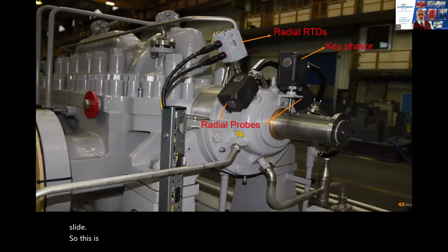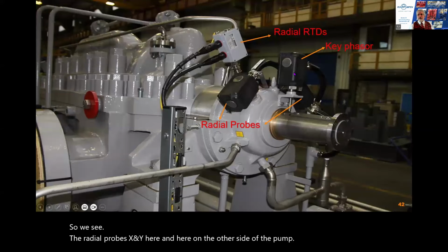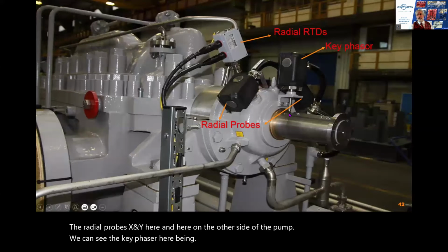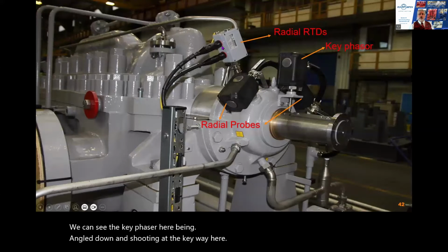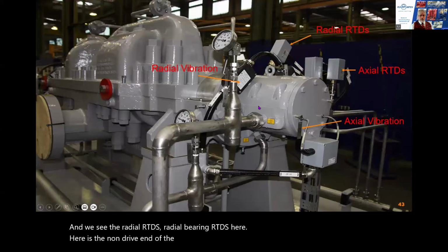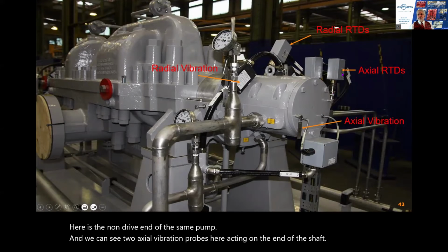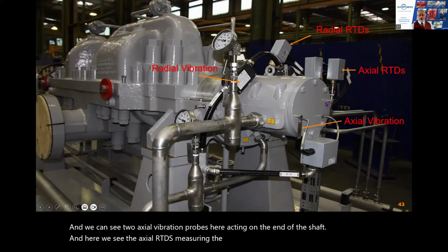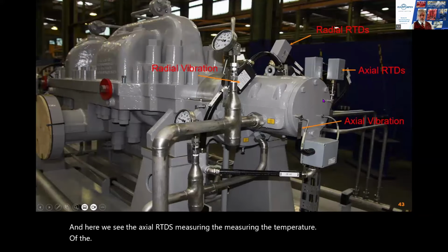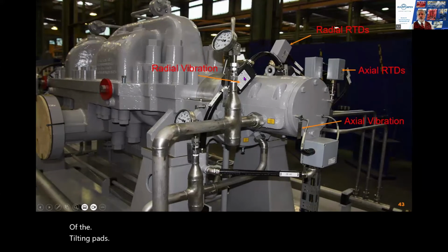So this is another example of a pump with sleeve and tilting pad type bearings. So we see the radial probes, X and Y, here and here on the other side of the pump. We can see the key phaser here being angled down and shooting at the keyway here. And we see the radial bearing RTDs here. Here is the non-drive end of the same pump, and we can see 2 axial vibration probes here acting on the end of the shaft. And here we see the axial RTDs measuring the temperature of the tilting pads. Again, we see the radial vibration probes here, another one on the other side.